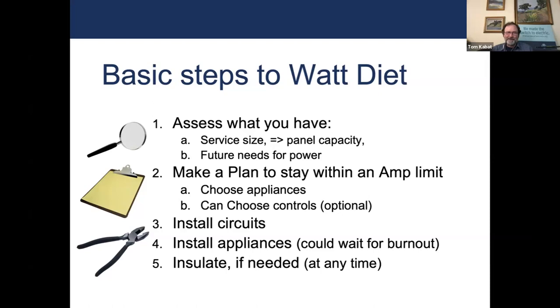All right, thanks. So the basic steps are to assess what you have. The first thing you might look at is the panel capacity you have, and the service wire capacity that feeds it - these are the constraints you want to stay within. A lot of people find they have either a 100, 150, or 200 amp panel, just by seeing what it says on the main breaker that has the service disconnect on it.